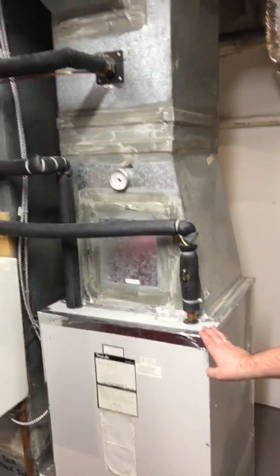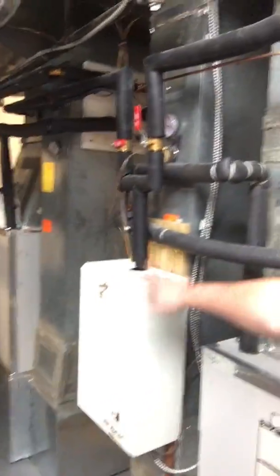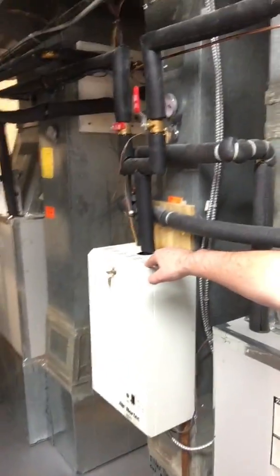It's got a high efficiency filter in it, a MERV 13 filter, and then it's also got steam humidification. This is a steam humidifier here, Nortec, very big fan of them. It's done pretty good for us over the years. Every once in a while you've got to rebuild them. That's just the way steam humidification works. We don't use evaporative humidifiers. We don't specify them on our jobs. Don't use them in my own house. The bacterial risks are too high, so we use steam. Steam is a nice way of keeping those little bugs and nasties from growing.